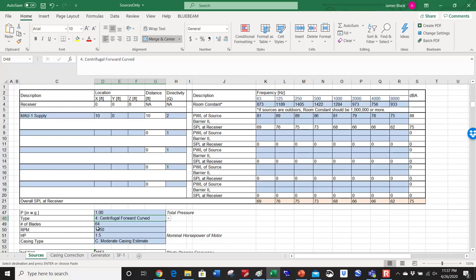Horsepower of the motor is a critical one. These two are going to combine to give us the blade passing frequency, which I'll explain in the slide coming up. Horsepower is just the nominal horsepower of the motor, and that's a big component in it. All of that is how you calculate the bare fan sound power level.